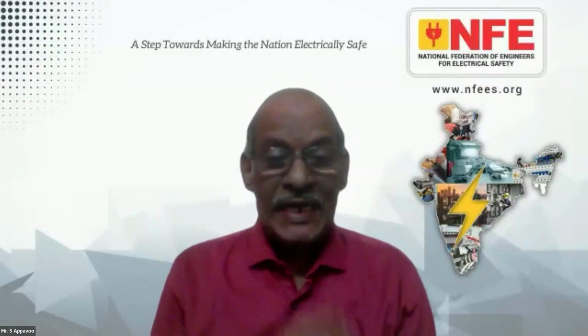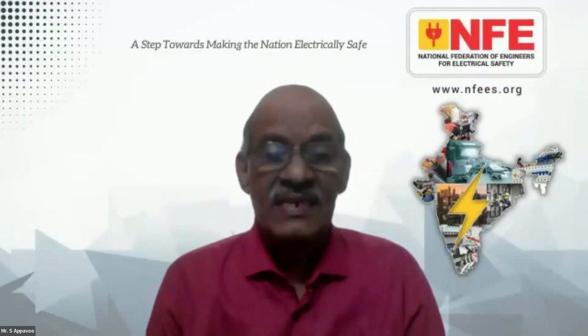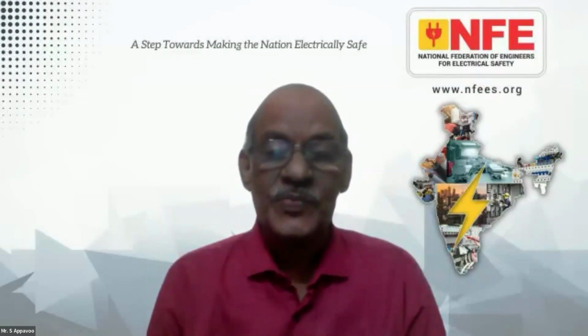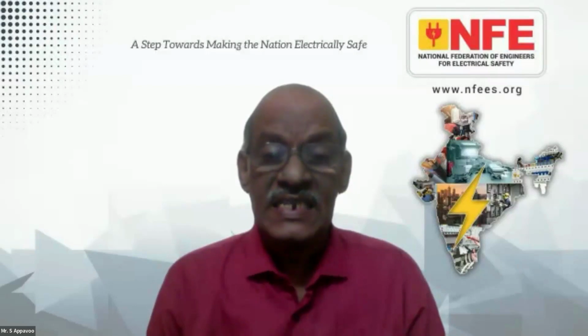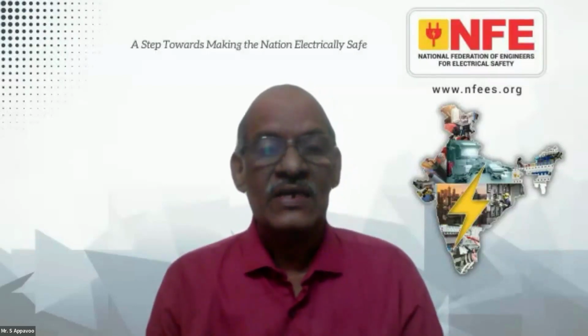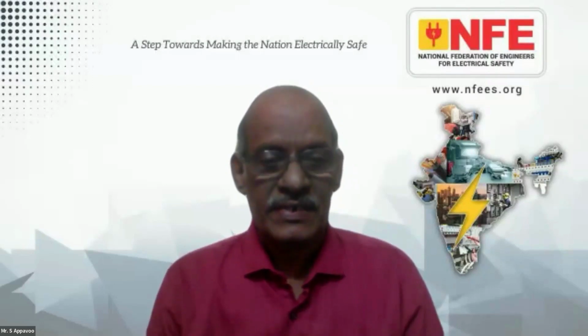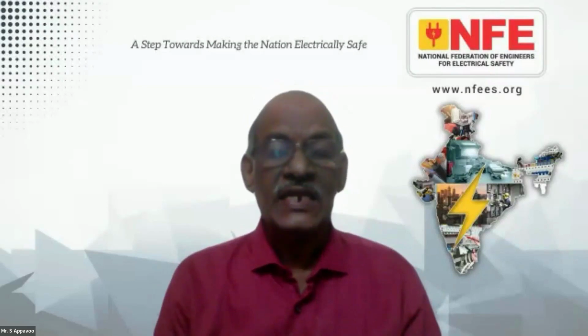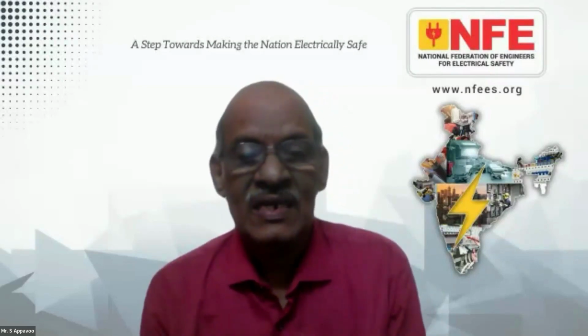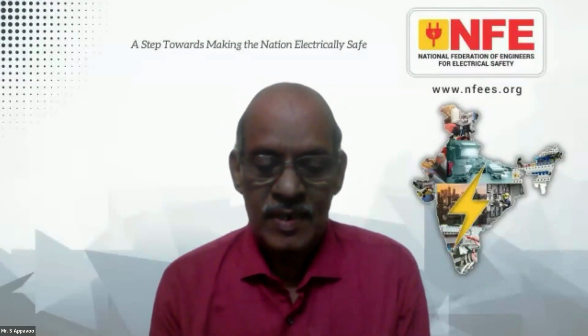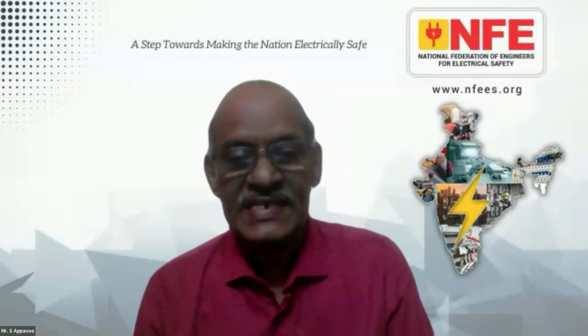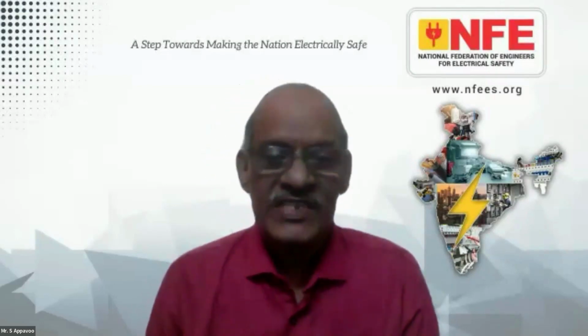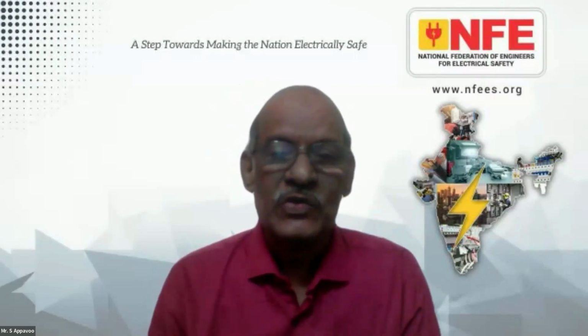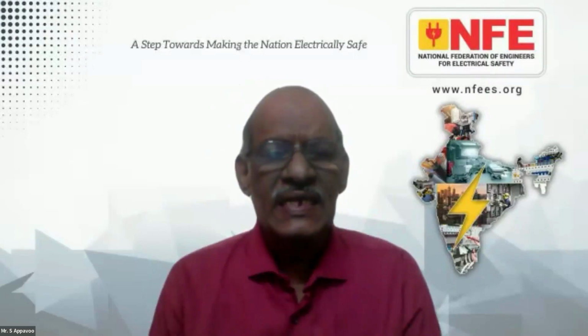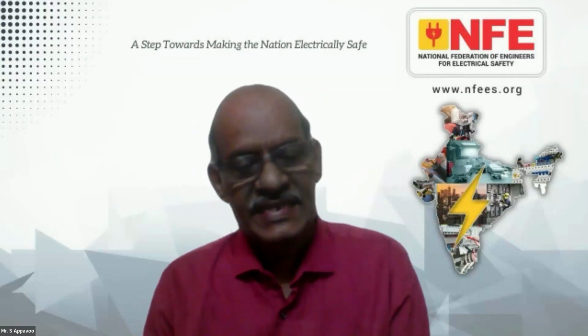Once you do the interconnections, it can't be generalized. You can adopt the measures which specify where interconnection is needed and in certain locations where insulation is required. We can't generalize within the question answer session. It requires a lot to be dealt with: whether your communication cable is involved, whether your pipeline is involved from the substation to a remote location, whether your fencing is accessible to a passerby, and whether your building is closely located to the substation. Go through EN 50522 and you can have a fair idea. Then we can have a separate session for EHV design.